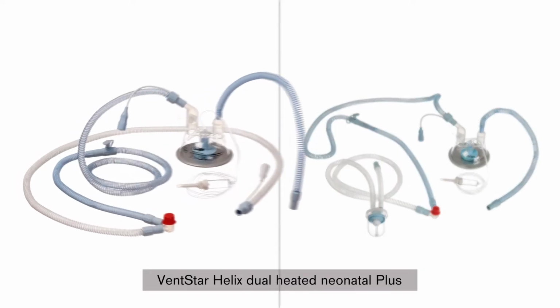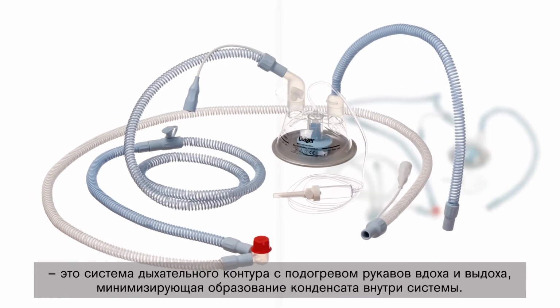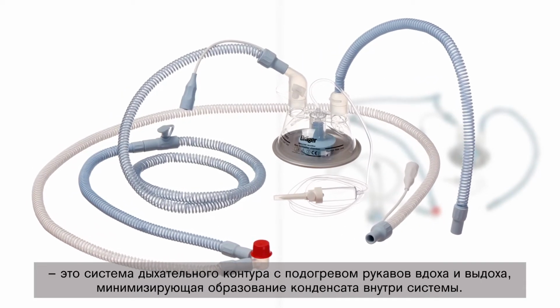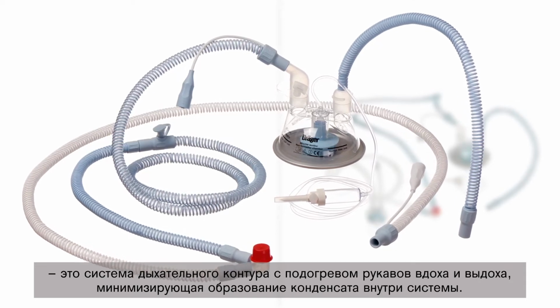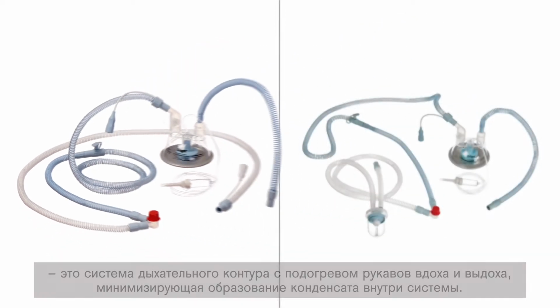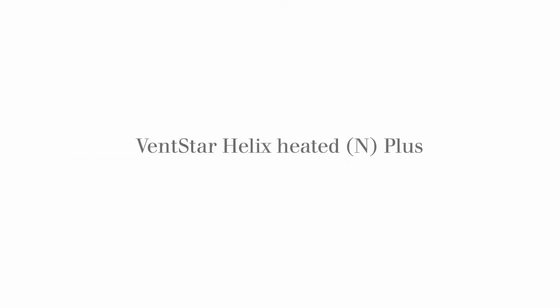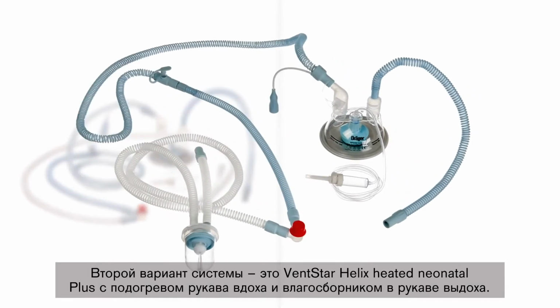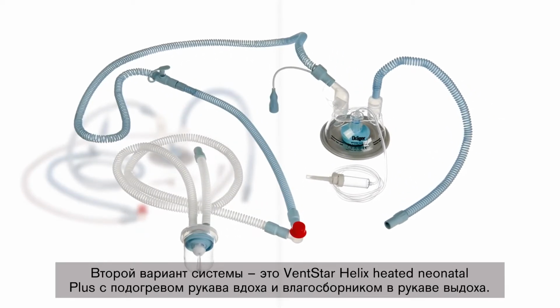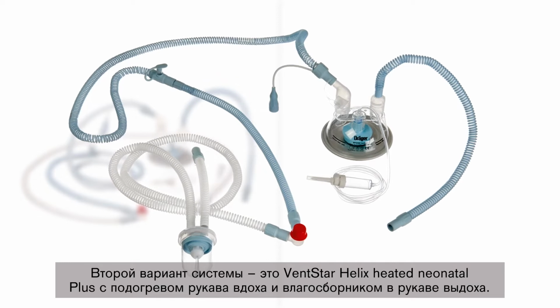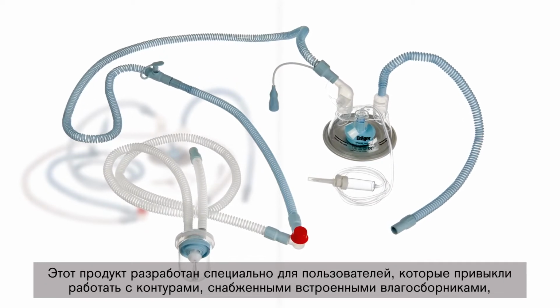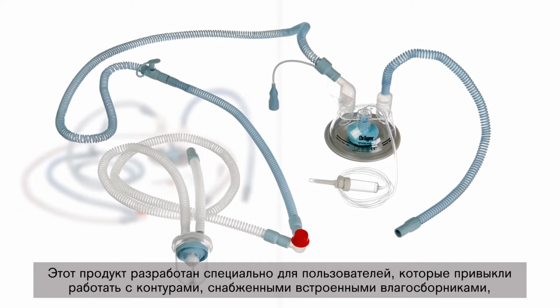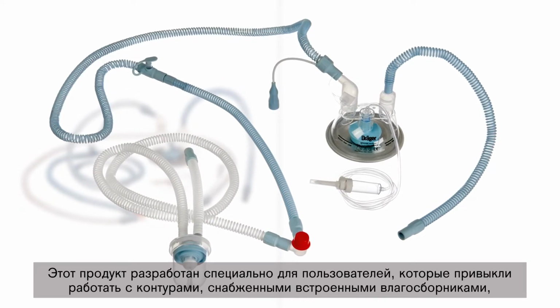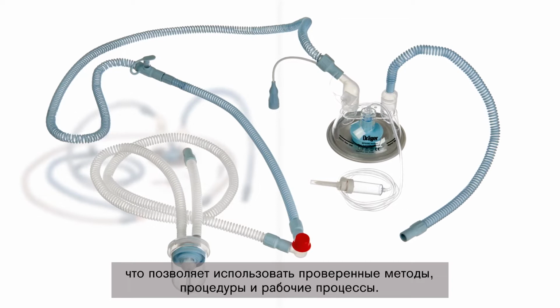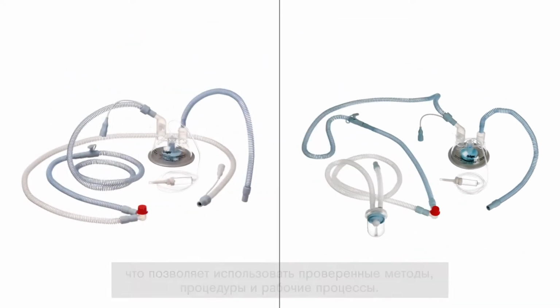The VentStar Helix Dual Heated Neonatal Plus is an inspiratory and expiratory heated breathing circuit system that minimizes the development of condensation in the system. The second circuit variant is the VentStar Helix Heated Neonatal Plus with integrated water trap in the expiration of the system. This product is designed especially for users who are accustomed to working with circuit systems that have integrated water traps, making it possible to maintain established practices, processes, and workflows.